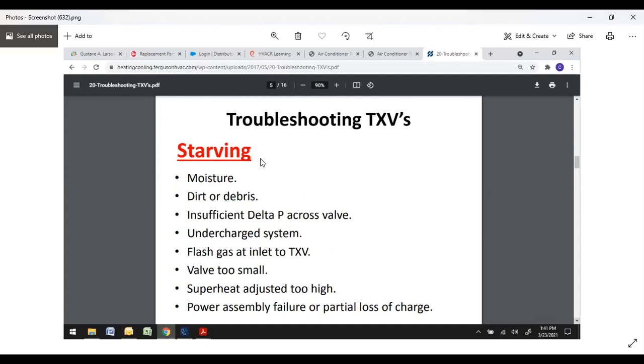So if you have a starved evaporator, it could be due to moisture, dirt, and debris causing the TXV to close. Insufficient delta P across the valve. Could have an undercharged system, because TXVs are funny. When you're charging them, sometimes as you're charging it, your suction will go really high. You think, I got too much in here. Your TXV will throttle as it needs to maintain the proper superheat based on your subcooling.